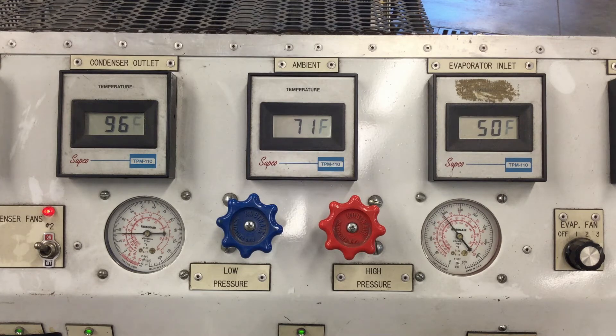It looks like the high side pressure is dropping just a little bit, and right about now the restriction is going into the system. You can see the low side pressure going into a vacuum and the high side pressure dropping from about 180 down to about 150 PSI. The TXV is currently being restricted all the way, so the low side is going into a vacuum.